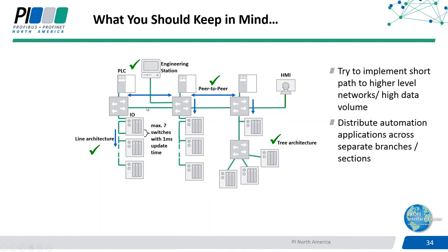Now, one way to help this high network loading is to implement the shortest paths possible for your devices which send a lot of traffic or stream. The best way to get rid of that HMI sending thousands of bytes through this line is to move it up here at the top, closer to the actual controller it's talking to, or the vision systems, whatever. So instead of putting it way out there, you want to move it closer, if possible connecting it closer to your controller if it's talking to the controller. You can also use multiple controllers or switches on your network to distribute the traffic across separate sections.